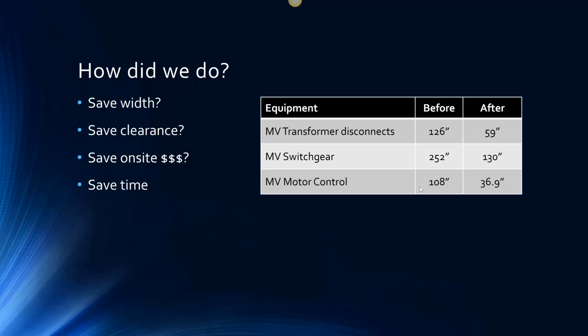And we saved quite a bit of space as well on the medium voltage motor control. Those 36 inches of AmpGard contactors were going to cost us 108 inches of linear width. And we got that all the way down to 36.9 inches.